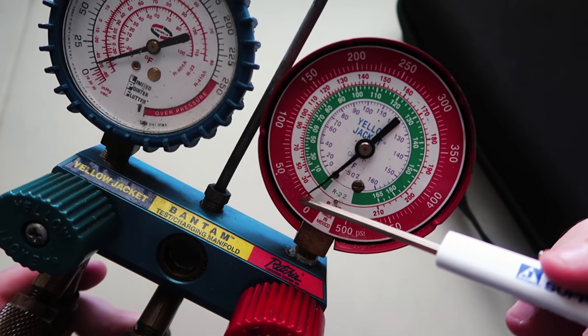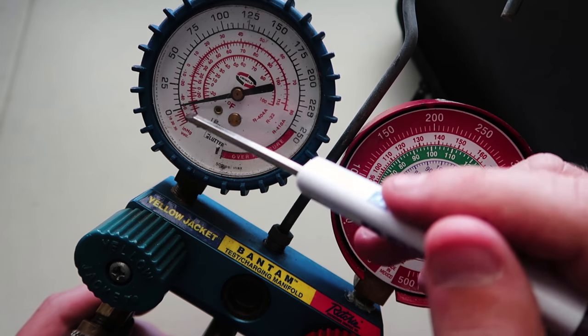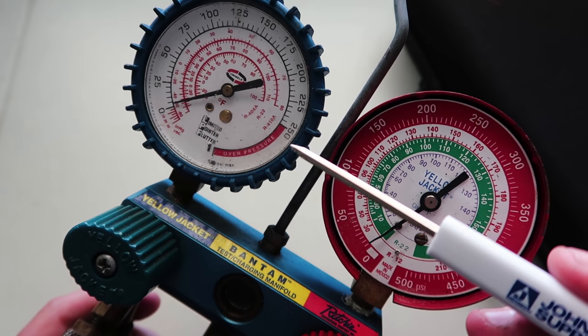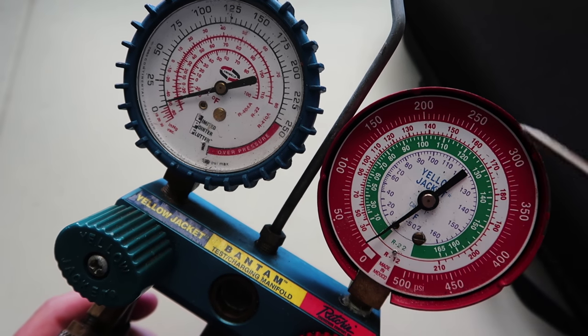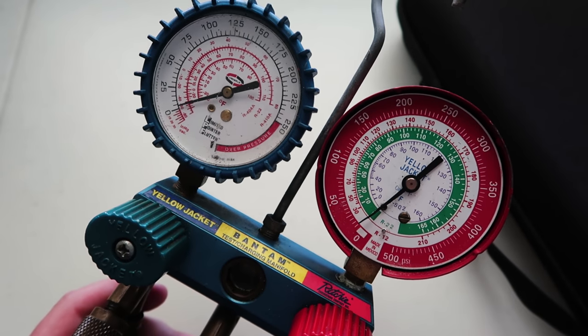Same thing here on the high side, you see that the gradations change, so it's from zero to 50 here, and here zero to 50 is a much wider range. So you see this goes all the way up to 250 psi before it starts to go into overpressure. This one here goes all the way up to 500 psi, which is pounds per square inch gauge.